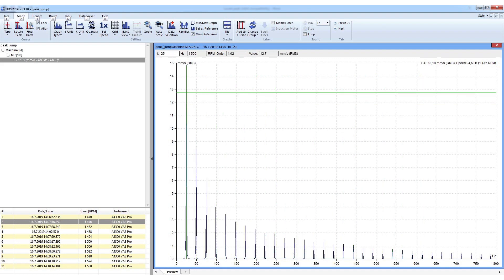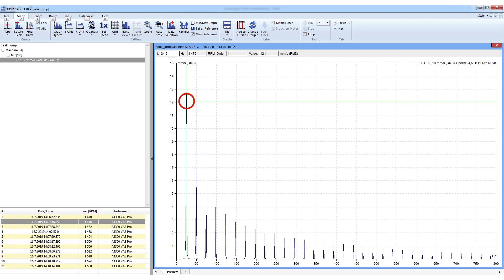The faster solution is the locate peak function. Place the main cursor to the speed peak line in the spectrum, then push the locate peak button. You can see that the main cursor position changed — now it is again exactly 24.6 Hz.